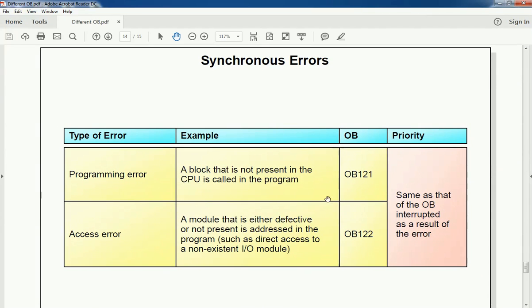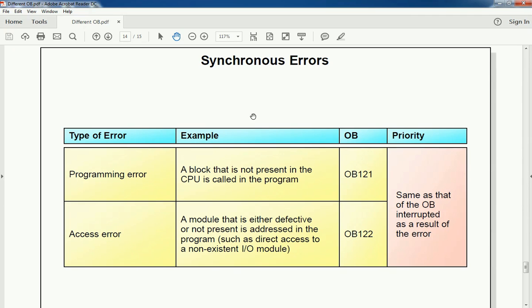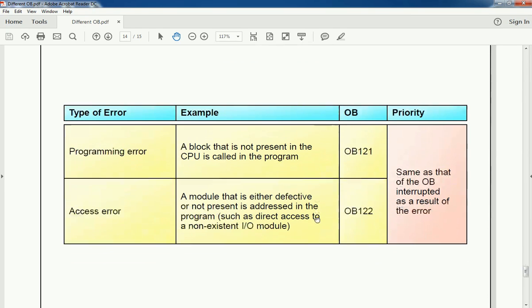Synchronous errors are programming errors or access errors. For example, if a block not present in the CPU is called, that is a programming error. If a module is defective or not present at the address in the program, that is an access error. Synchronous error OBs OB121 and OB122 have the highest priority and execute first, then lower priority OBs, and finally OB1 executes. This is the continuous flow of the main OB and different OBs used in PLC. Now we will see practically how to execute the program and use OBs in PLC.